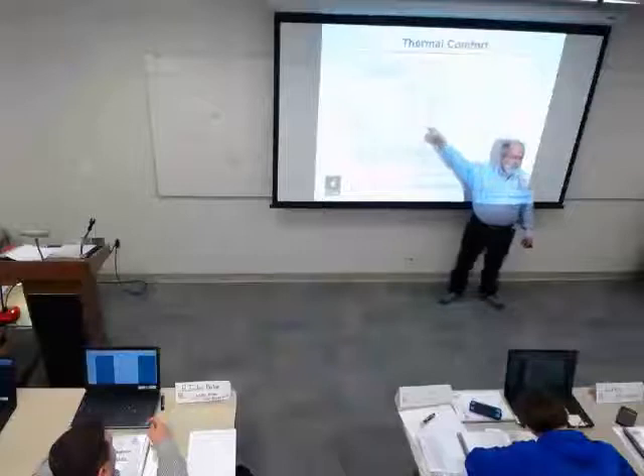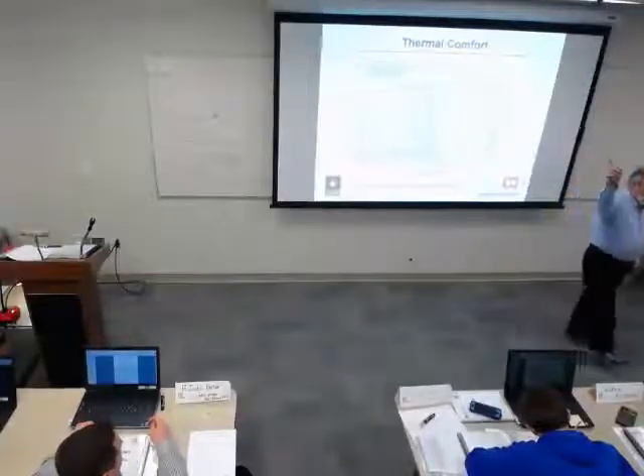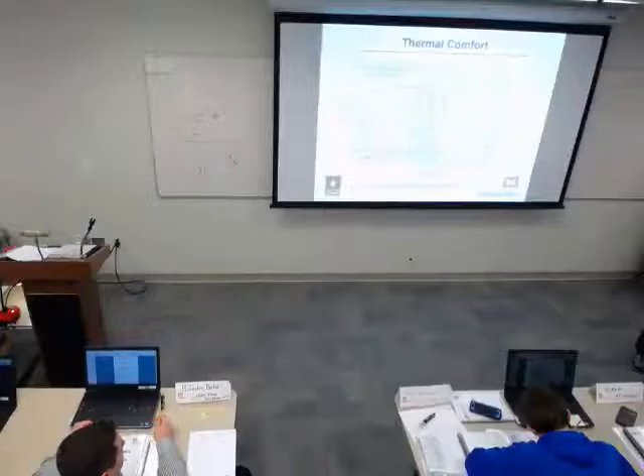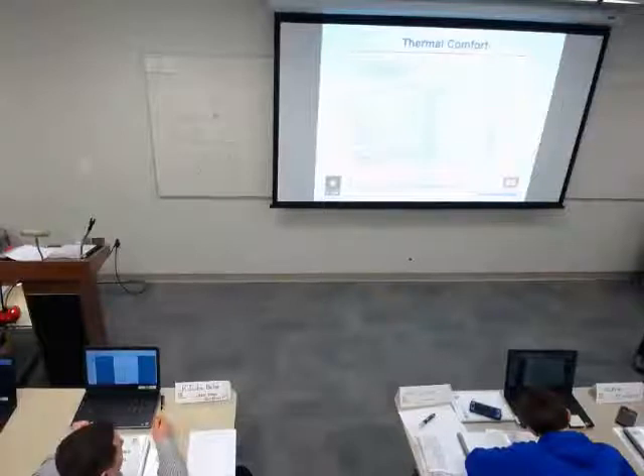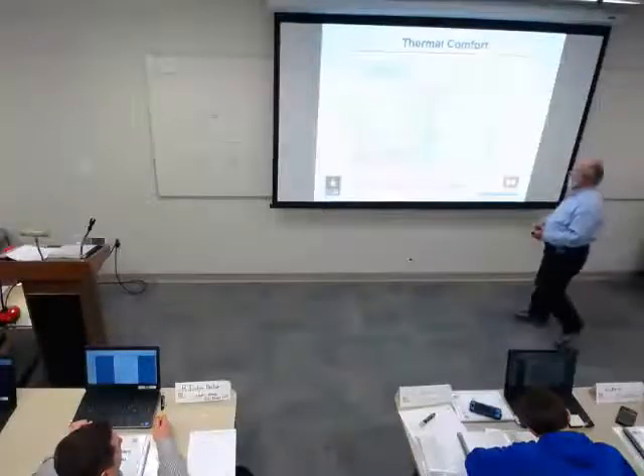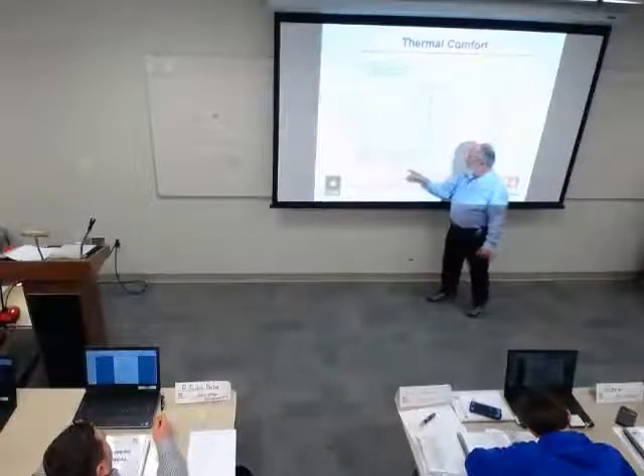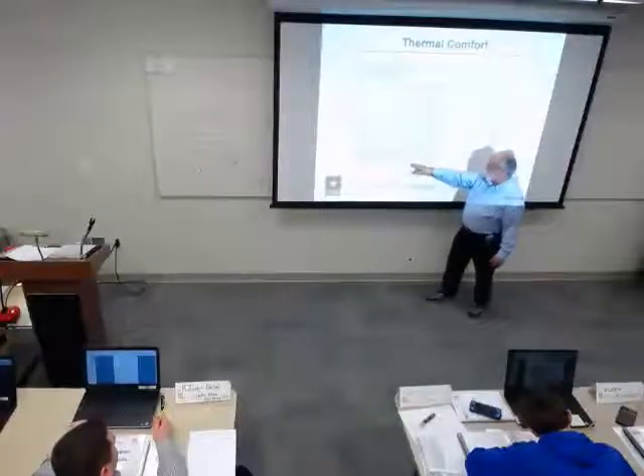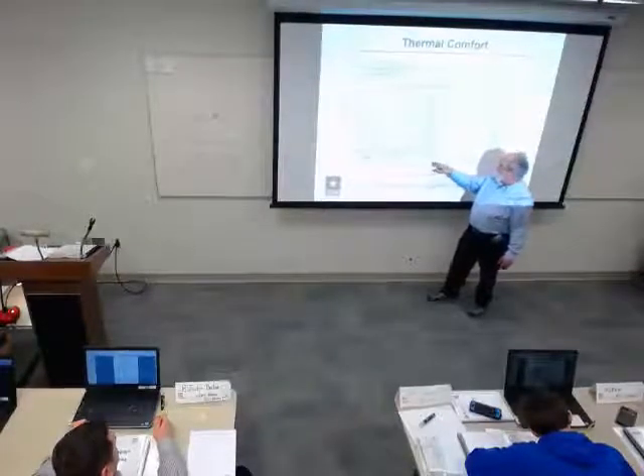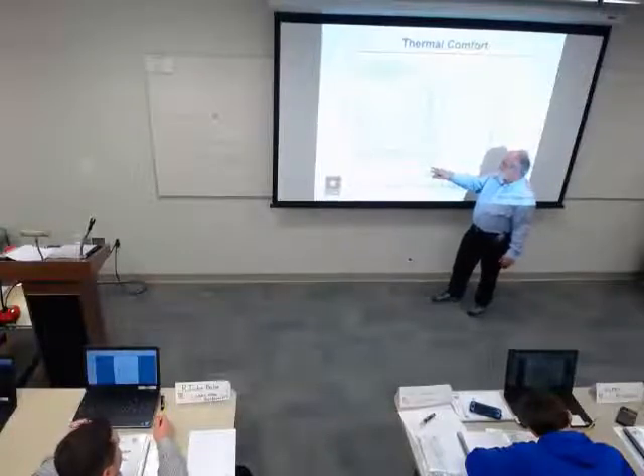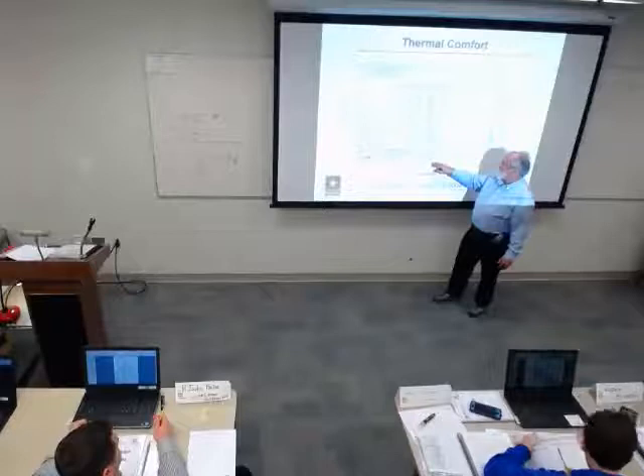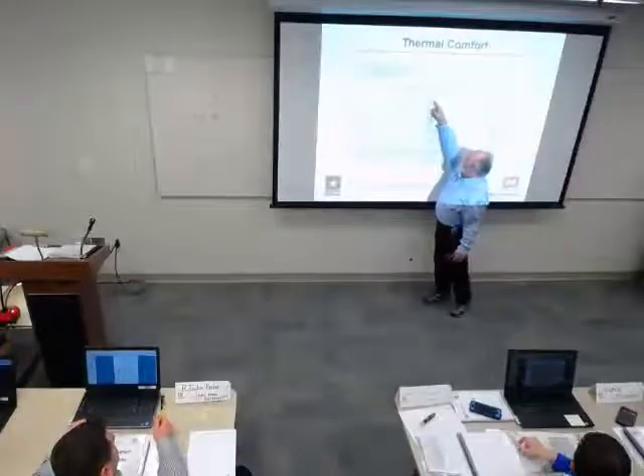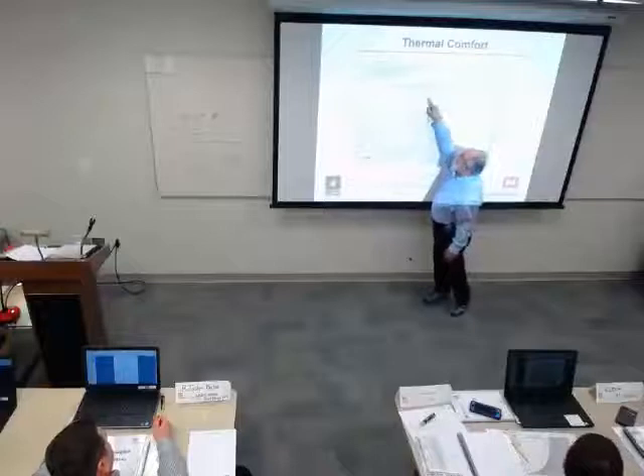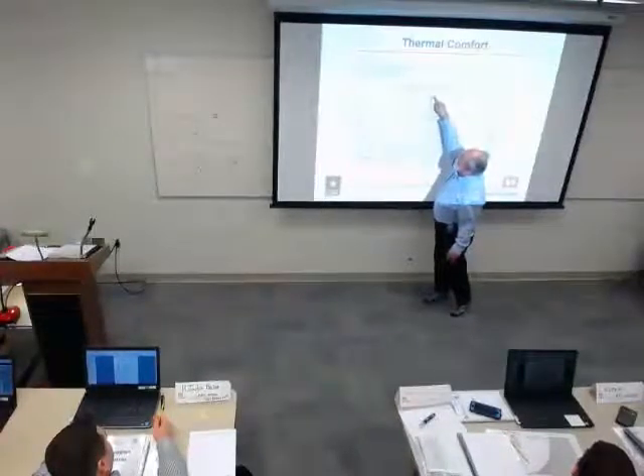We have a way of rating clothes, and I believe that's in ASHRAE 55 also, in which for any given clothing combination for male or female clothing, you can come up with a clo rating, which is basically a kind of insulation rating for clothing. And so here for a clo rating of about 1, you have something that goes from about, let's see, that's about 1% relative humidity, 71, up to, and right here's where that goes to about 78, 77, something like that, 1%. And then we go up here at the high end, and we're sitting at, let's see, that's 70% there, 60% there, that's 65%.